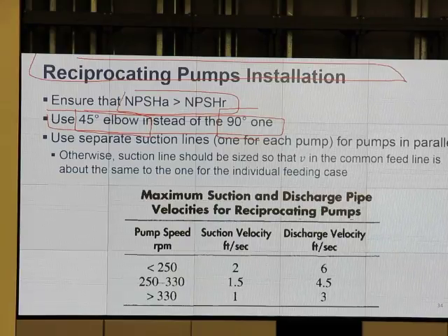Okay, if we flow this way and up, the fluid direction changes quickly. But if we do 45 and another 45, it changes slower. That is less pressure drop. If we just use a hose that curves like this, even lower pressure drop. So whenever there's a quick change in the direction, that's the place for the flow pressure drop. So next to you, what's your name? Mackenzie. This kind of pressure drop, we account for it in what term?